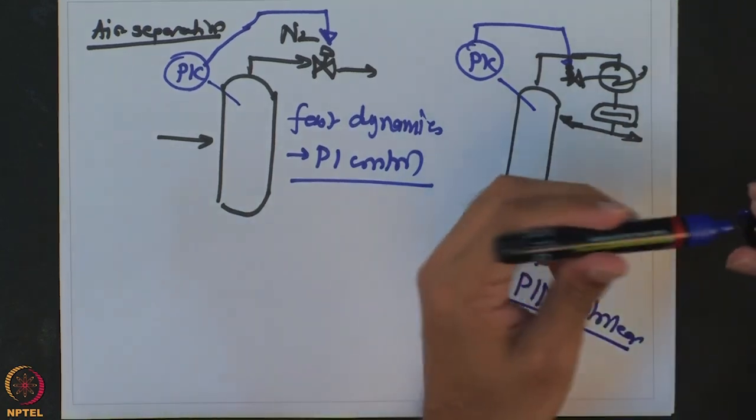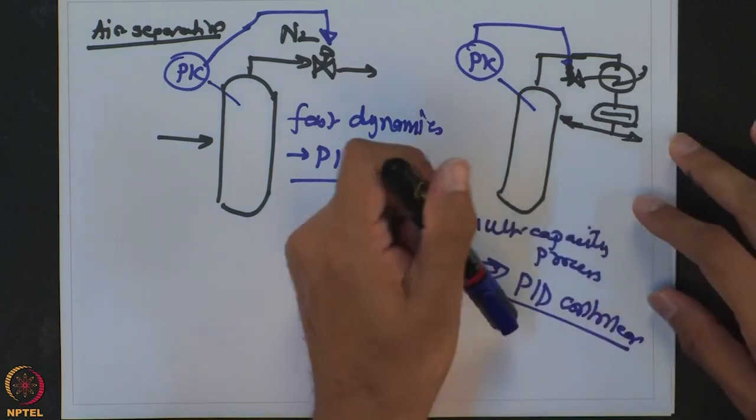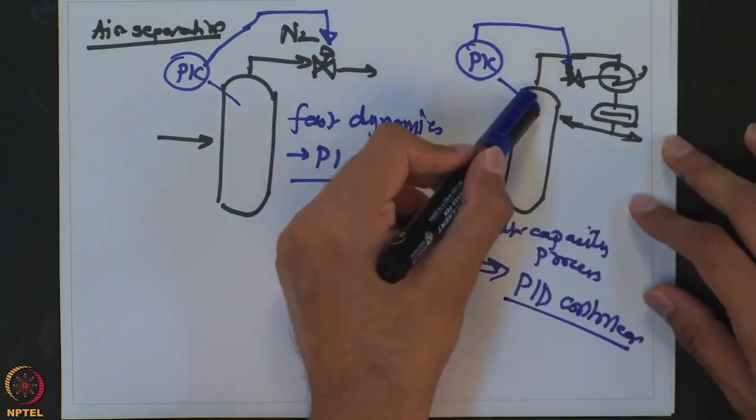Having said that, not every distillation pressure controller will be a PID controller, because you also have to weigh in whether offset is acceptable or not. A lot of times in high-pressure distillation, a small offset in pressure is not going to affect the extent of separation, so you may even go with a simple P controller.